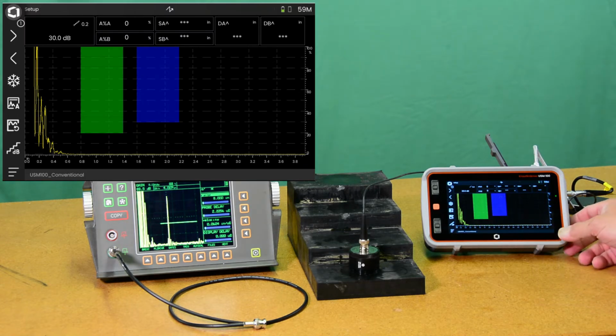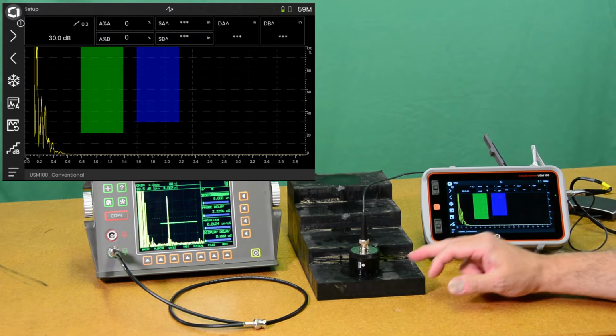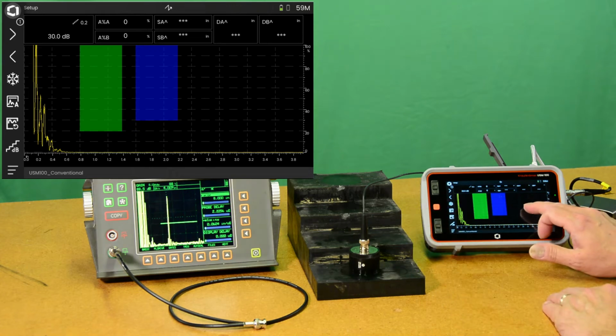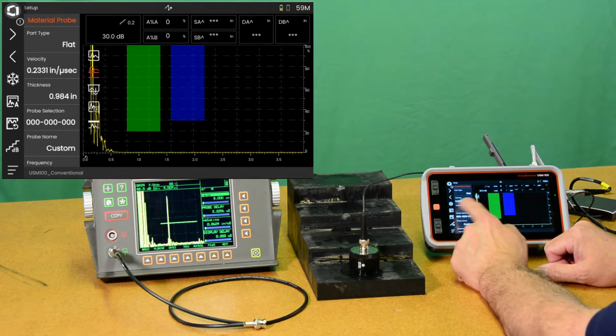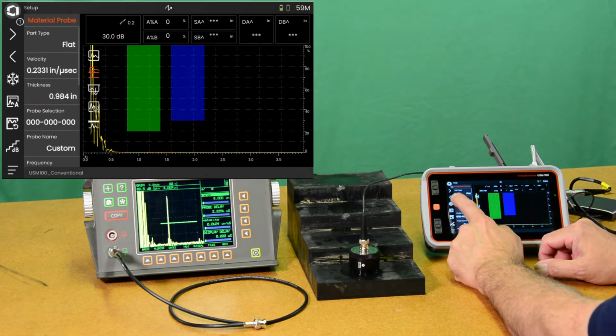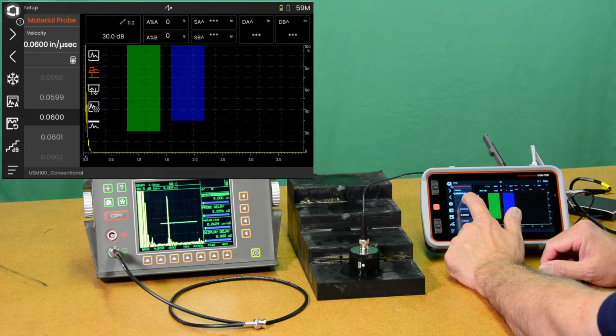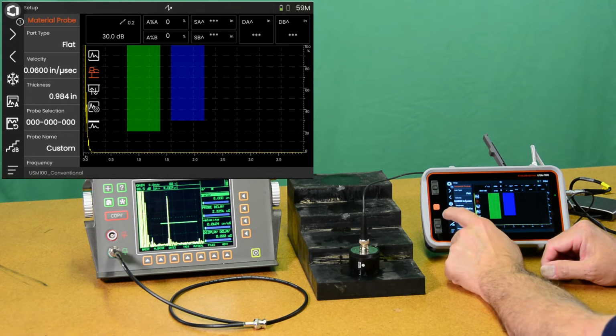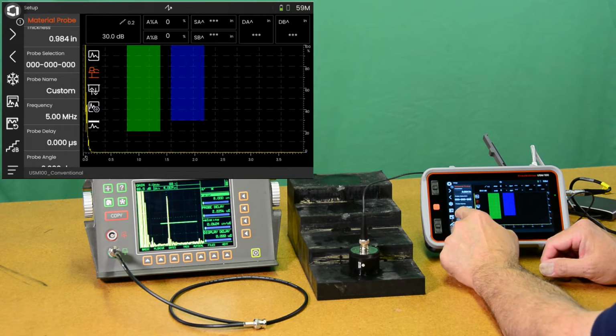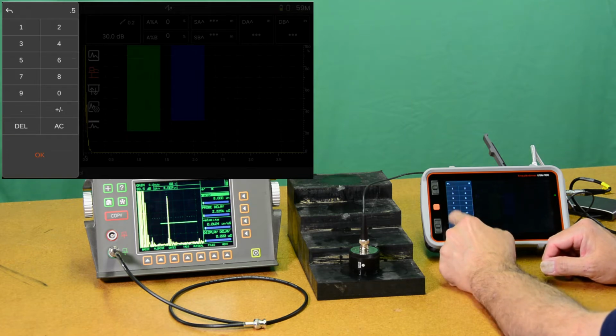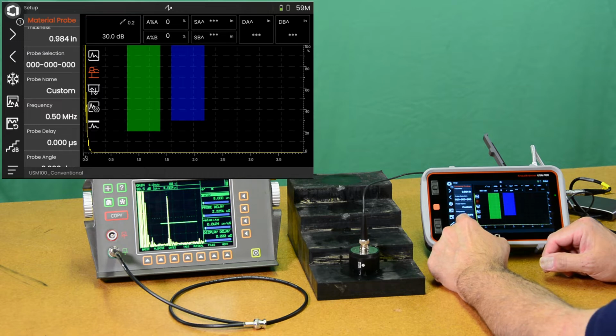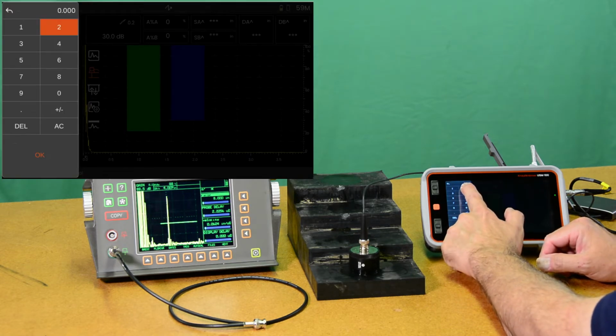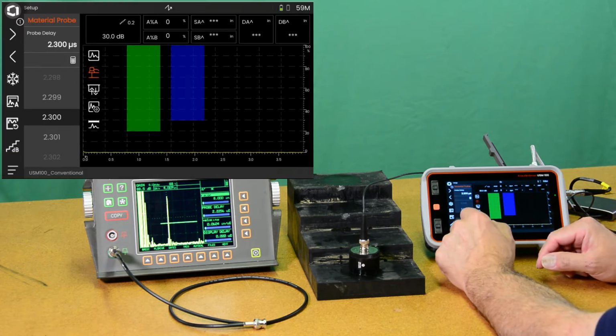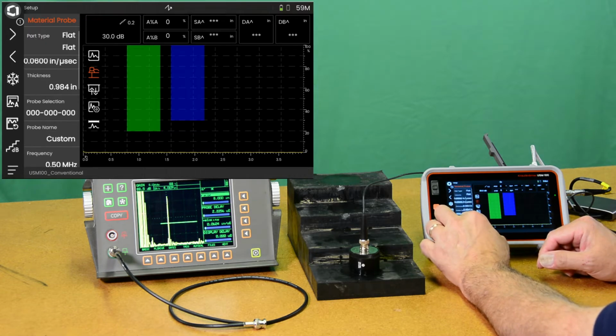So a couple of things that we need to do. First thing we're going to do is set up and tell it something about this probe. Okay, so I touch the A scan to open the menus, and I'm going to choose the probe menu to start. We have a flat part. We're going to set our velocity to 0.06 inches per microsecond. I happen to know that the rubber is approximately 0.06 inches per microsecond velocity. Close that. We're going to tell it that the probe frequency is 0.5 megahertz. Okay. We're going to tell it that the probe delay is approximately 2.3 microseconds. That's a property I just happen to be familiar with in this probe. And the rest of that menu is fine.